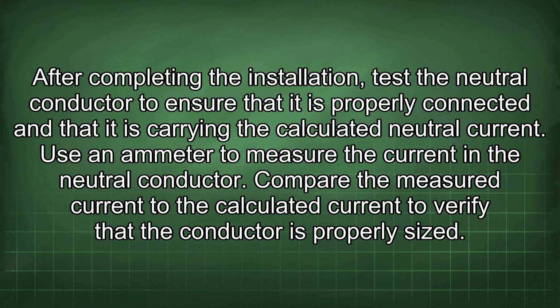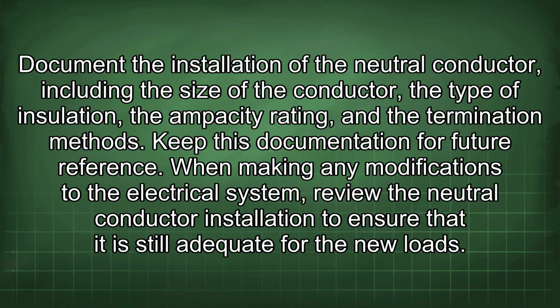After completing the installation, test the neutral conductor to ensure that it is properly connected and that it is carrying the calculated neutral current. Use an ammeter to measure the current in the neutral conductor. Compare the measured current to the calculated current to verify that the conductor is properly sized. Document the installation of the neutral conductor, including the size of the conductor, the type of insulation, the ampacity rating, and the termination methods. Keep this documentation for future reference.